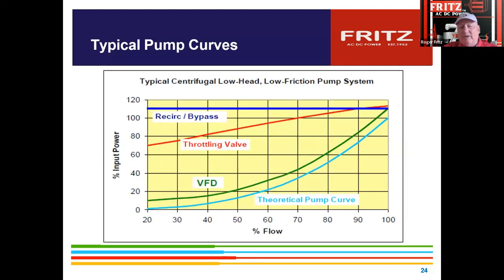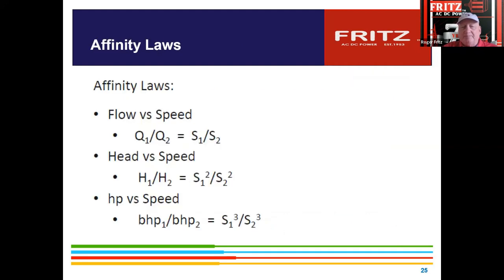And then this is more of a typical pump curve with a VFD, but it just doesn't show in here. We have software that actually shows where the sweet spot is to run the VFD in, so that you design it, you set your upper and lower limits so that they stay in that sweet spot of operation. These are the affinity laws.